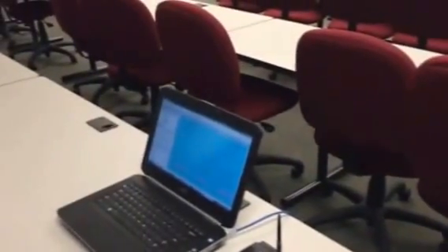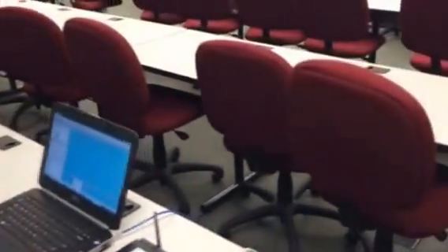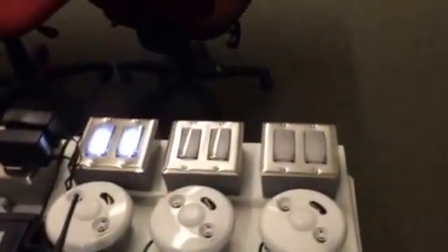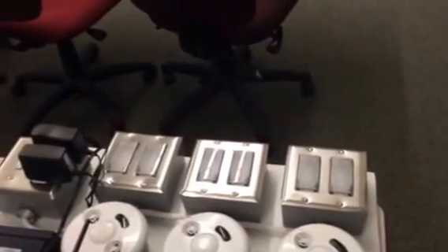Here's our segment manager, and then he's built just a PX page in the Niagara framework that is our segment manager. He's just built a simple user interface. And Elliot, what I'd like for you to do is just start off by demonstrating how, just through a normal browser, we can control loads in the DLM rooms. So he's just going to communicate to the segment manager across Ethernet, through the Ethernet switch, the MSTP bridge, into the DLM rooms, and he's activating loads on and off through a browser that can be located anywhere.